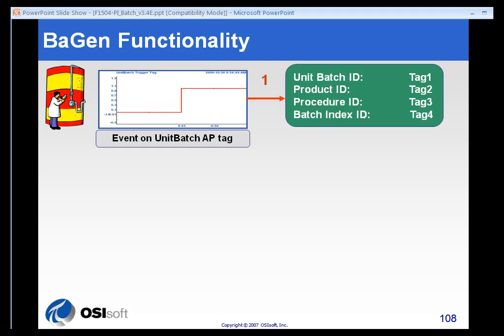The PI batch generator will then go look at four different tags: one tag for the unit batch ID, one tag for the product ID, one tag for the procedure or recipe ID, and finally, optionally, if this unit batch belongs to a larger batch, it will examine a batch index ID tag.